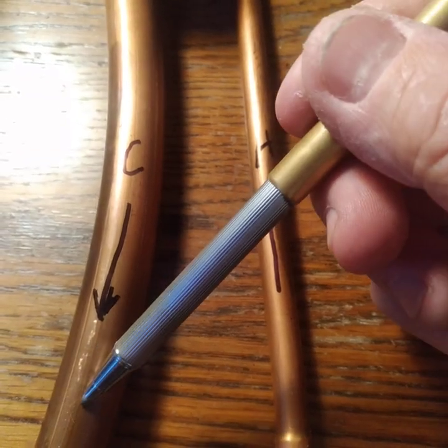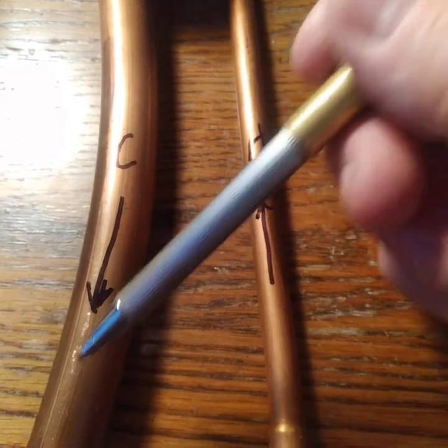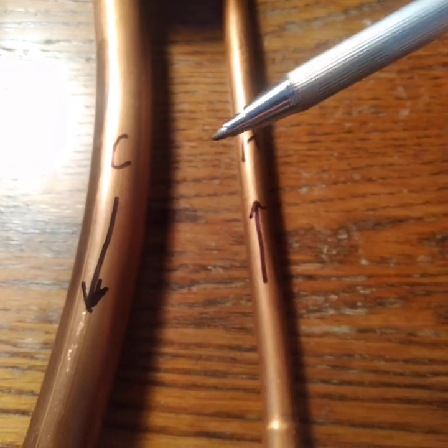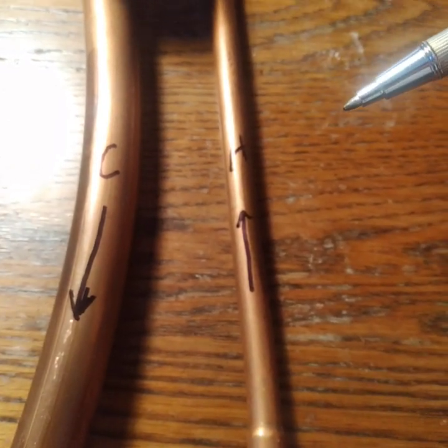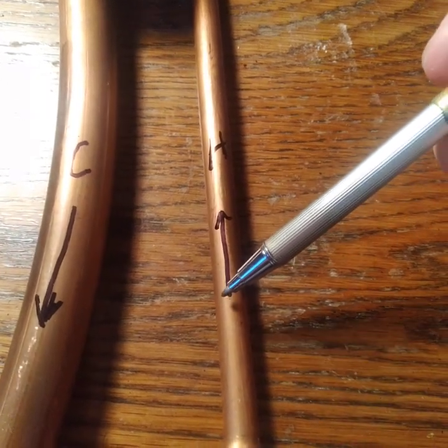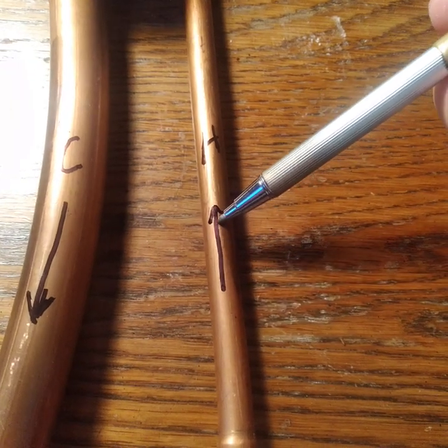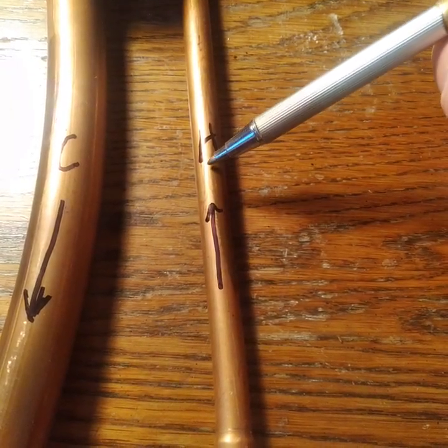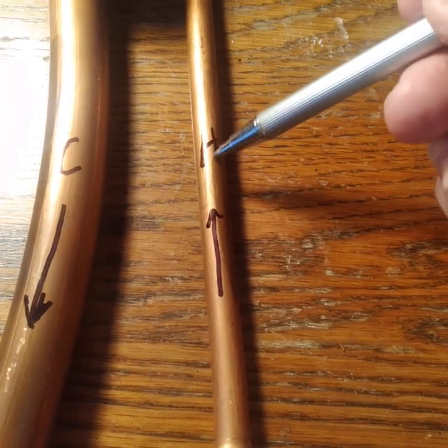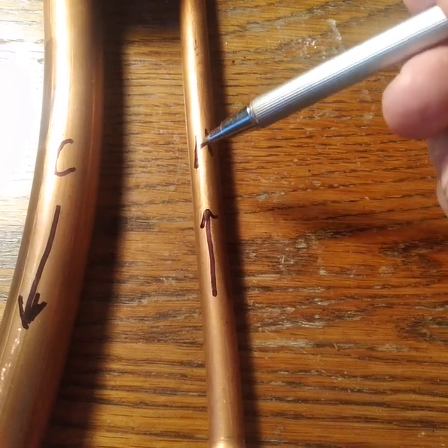Once it goes to the outside, again, it goes through the compressor as a low pressure vapor, compresses it, comes out as a high pressure vapor. The heat is dissipated by the fan, the condenser fan motor, and the air blowing over the coils. It comes down and it begins to turn into liquid. So this is the liquid line or the high pressure line, and we've got H just as a nomenclature for hot. You can put warm, hot, whatever you want to put.